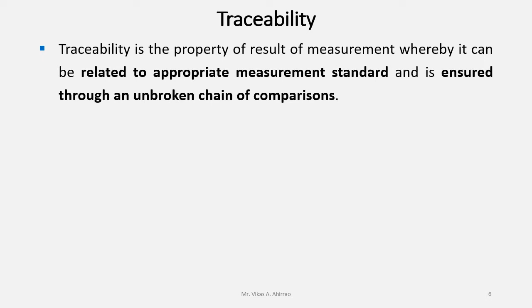Traceability is the property of result of measurement whereby it can be related to appropriate measurement standard and is ensured through an unbroken chain of comparisons. An industrial equipment or a process equipment may be calibrated in an industrial lab using its own standards. If not, this needs to be calibrated with a higher accuracy standard in another lab. The standards in the lab in turn should be calibrated with a still higher accuracy standard, and so on until the chain ends when a laboratory standard is calibrated in the primary calibration lab of a country. The diagram shows the traceability chart.